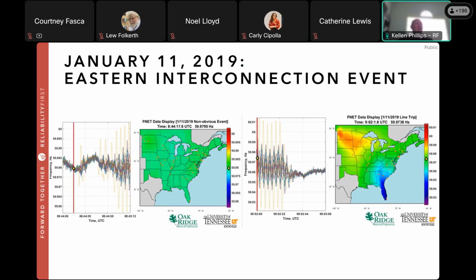Now, what caused it? A failed potential transformer, also known as a PT connection, and an erroneous voltage measurement in the controller meant that the controller thought there was an imbalance, so it shut valves, waited 4 seconds, reopened them. The controller still thought there was an imbalance, so it closed them, waited 4 seconds, and reopened, then closed, and so on and so on. This meant the steam turbine at the combined cycle plant oscillated for about 18 minutes until a local plant operator removed the unit from service.